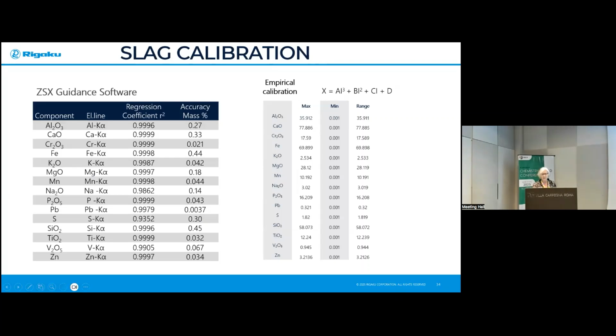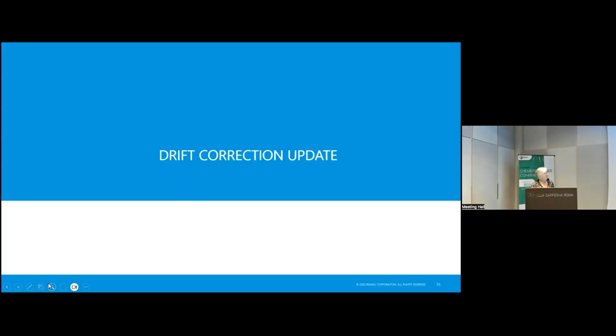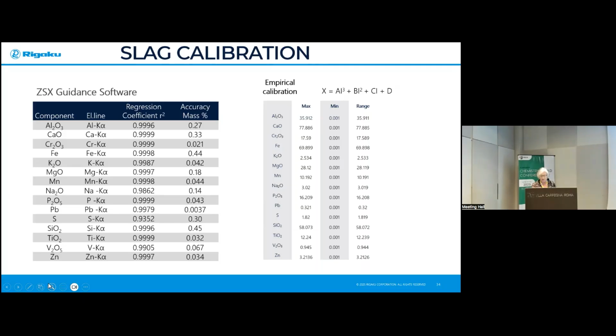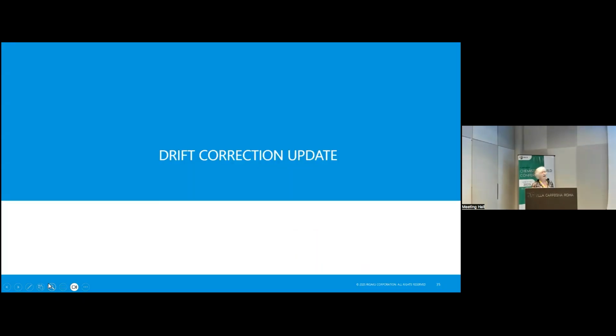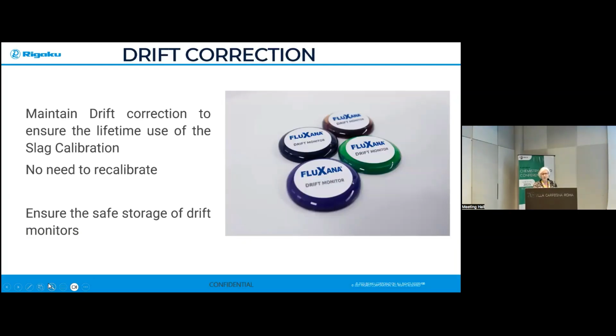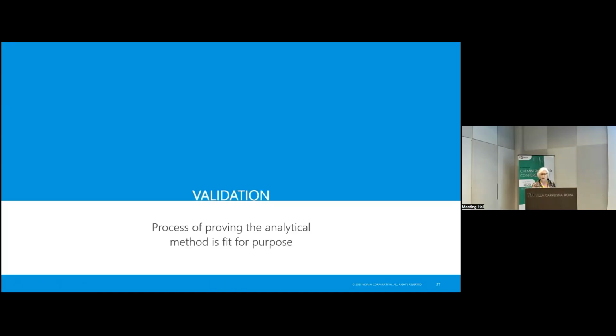And here's a summary of the regression. So you can see very, very pleasing and excellent regression with very good accuracy for all the oxides that we would like to measure in the slag. Well, one of the biggest advantages with X-ray fluorescence is that you spend a lot of time to create these perfect calibrations, but now we can compensate for the intensity change by using a drift correction. So this is like a method that's used in X-ray fluorescence to ensure that we can update our spectrometer with the change of intensity. So we can use the calibration for a long period of time.